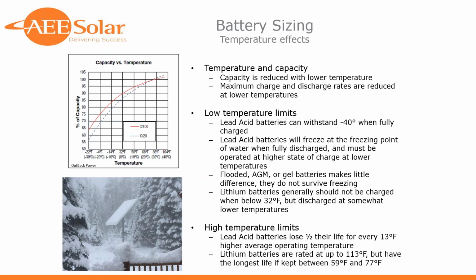High temperature limits: lead acid batteries lose half of their life for every 13 degrees Fahrenheit above their optimum operating temperature. That's pretty severe. And some of you may have seen that, where the batteries are really hot, they don't last very long. Lithium batteries are rated for up to a certain temperature. I don't know exactly how much life they lose at higher temperatures. They're best if they're kept at a fairly moderate temperature.